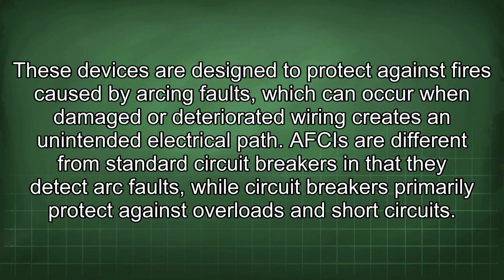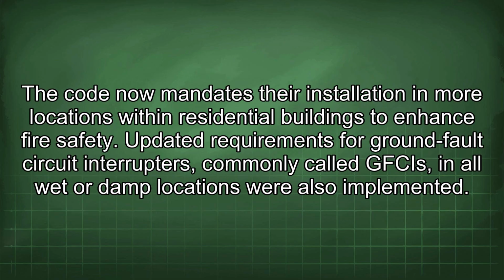AFCIs are different from standard circuit breakers in that they detect arc faults, while circuit breakers primarily protect against overloads and short circuits. The code now mandates their installation in more locations within residential buildings to enhance fire safety. Updated requirements for ground fault circuit interrupters, commonly called GFCIs, in all wet or damp locations were also implemented.